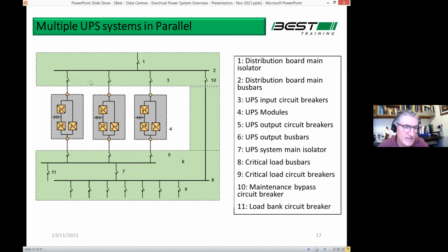And this system here, the switchgear, shows 3 separate UPS modules. You can see each one has an input breaker on the top, an output breaker, and then item 10 has a complete bypass system on it here. And then this busbar down the end that you see, all these lines here, they're going out, not directly to your server, but to the switchgear that in turn feeds your server. And that's where we're coming to in the next slide.